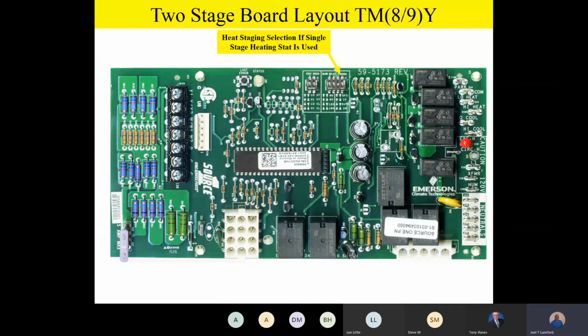Now watch this, I saved the best for last. If those dip switches are in the auto position, that plugs in some intelligence on the board. Inside the programming of that board, if those dip switches are in the auto position, when it gets a W call, it starts counting and monitoring the time that the thermostat takes to satisfy. And then it starts making intelligent decisions on when to stage to second stage. To give an example, let's say we had 3 cycles and it took 17 minutes to satisfy the thermostat. I'm just making that number up. Well, on the 4th cycle, it might run 8 minutes on first stage and then see how long it took on second stage to satisfy the thermostat, and so on. So this board starts learning thermostat activity and the optimal staging sequence by looking at the thermostat activity with a single stage thermostat.